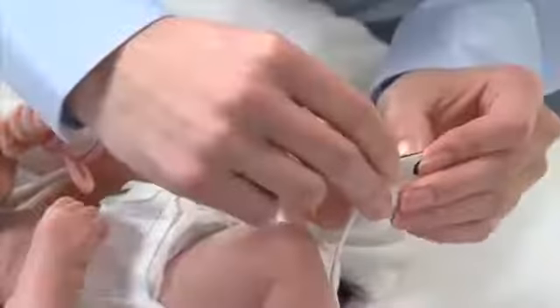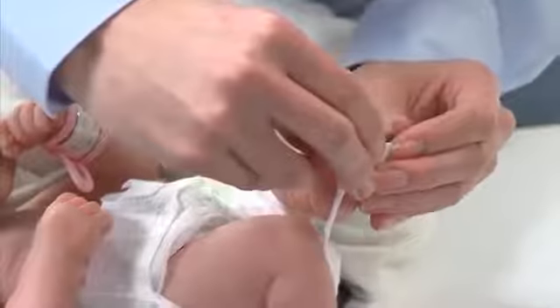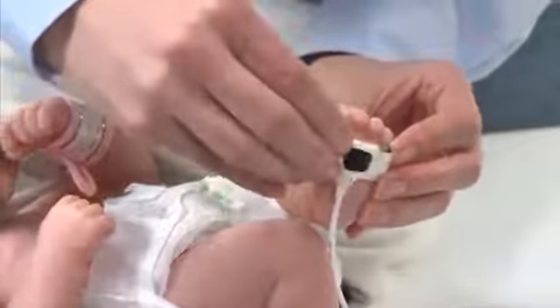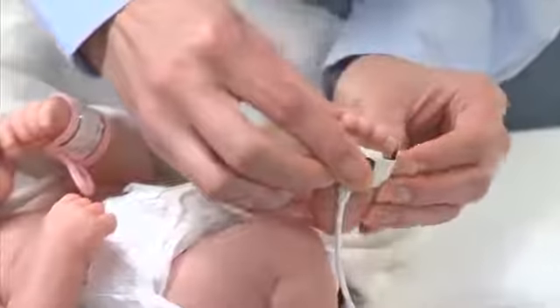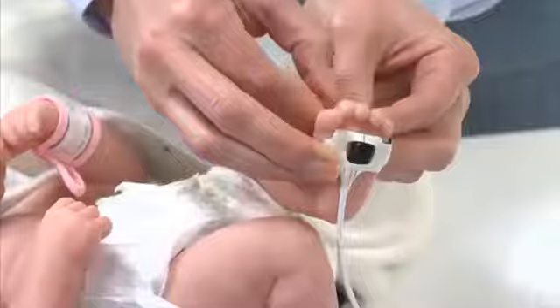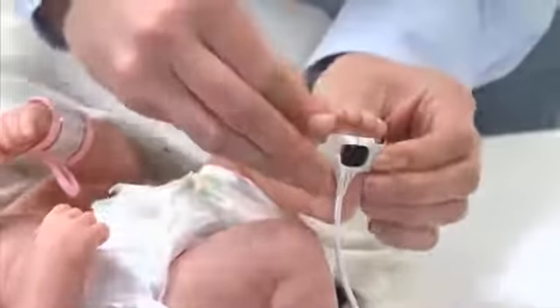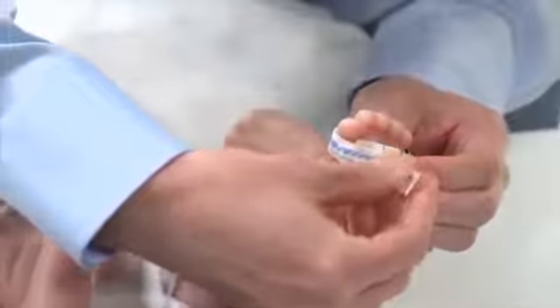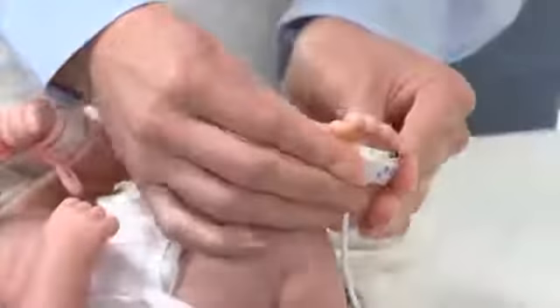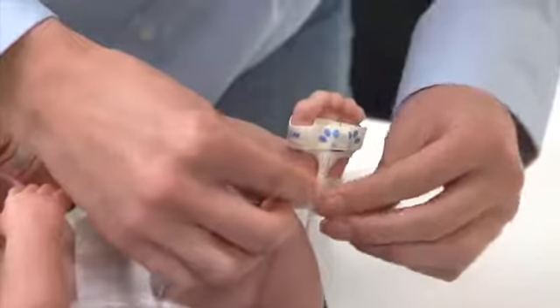For placement on the foot of a neonate 4 or less pounds in weight, place the adhesive and detector portion on the bottom center of the foot at the base of the toes with the cable running back toward the heel. Now, wrap the sensor on top of the foot, aligning the top portion with the sensor portion on the bottom of the foot. It's a good idea to gently secure the sensor cable independently from the sensor along the bottom of the foot or at the ankle, depending on the foot size.